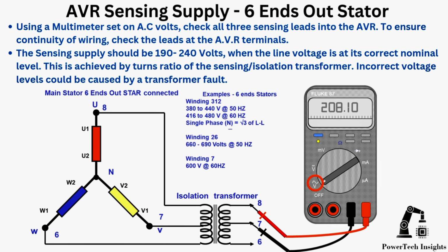AVR sensing supply, 6 ends out stator. Using a multimeter set on AC volts, check all 3 sensing leads into the AVR. To ensure continuity of wiring, check the leads at the AVR terminals. The sensing supply should be 190 to 240 volts when the line voltage is at its correct nominal level.